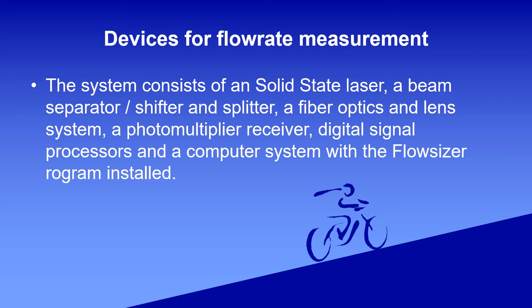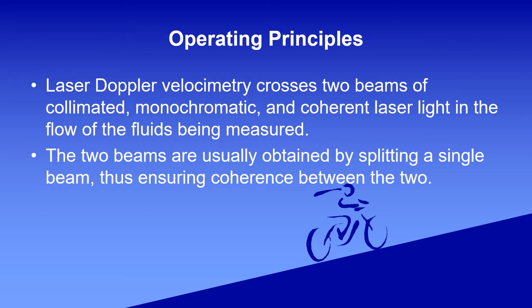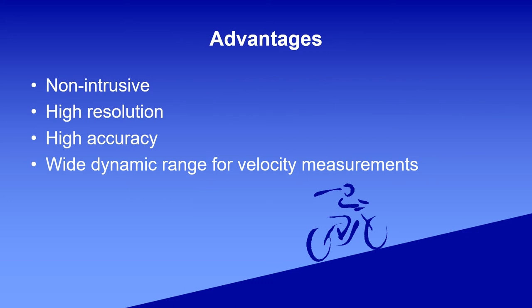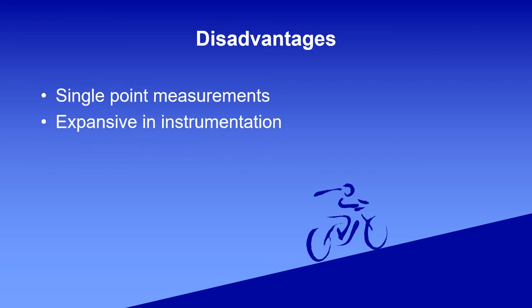The LDV system consists of a solid-state laser, a beam splitter and shifter, a fiber optics and lens system, a photomultiplier receiver, digital signal processors, and a computer system with the flow sizer program installed. The operating principle is that the laser Doppler velocimetry crosses two beams of collimated, monochromatic and coherent laser light — the two beams are usually obtained by splitting a single beam. The advantages are non-intrusive measurement, high resolution, high accuracy, and wide dynamic range for velocity measurement. The disadvantages are single point measurements and expensive instrumentation.